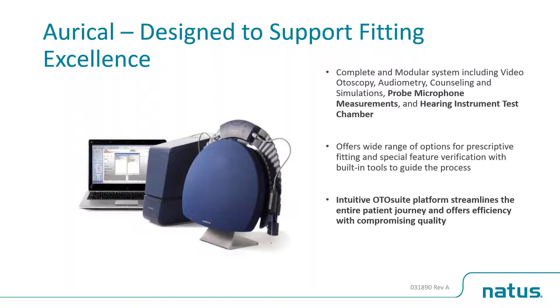So what are the hardware elements for a probe microphone measurement system? And this is going to be just beyond ours. These are just some basic hardware requirements for the real ear system. So for our system, you are going to see a FreeFit collar that does have the probes on it. So that is wireless. There is no wire from the device to the patient. Then you're going to see a speaker. So this blue underneath here, if you take off the cover, there is the free field speaker. On the probe itself, there will be the reference microphone and the probe tube that attaches to the probe itself.